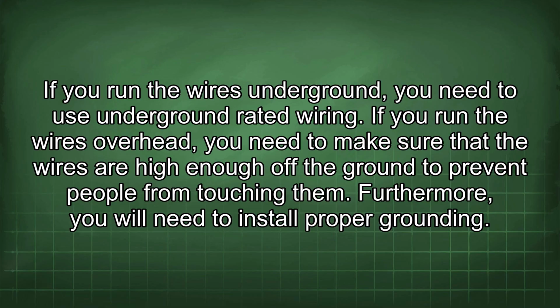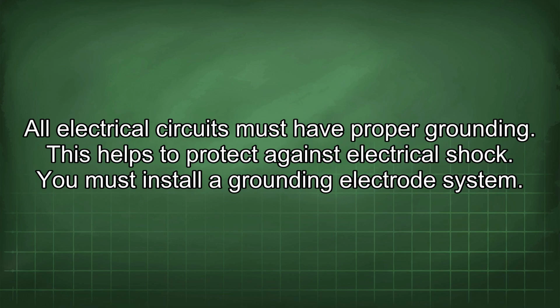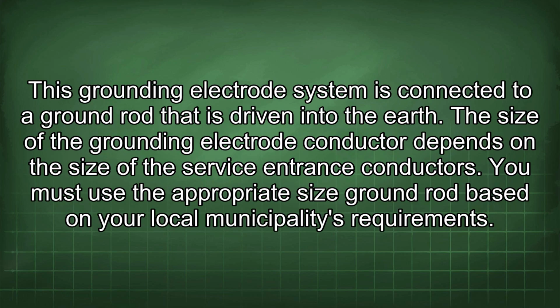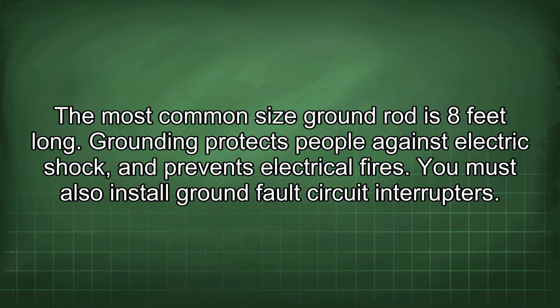Furthermore, you will need to install proper grounding. All electrical circuits must have proper grounding. This helps to protect against electrical shock. You must install a grounding electrode system. This grounding electrode system is connected to a ground rod that is driven into the earth. The size of the grounding electrode conductor depends on the size of the service entrance conductors. You must use the appropriate size ground rod based on your local municipality's requirements. The most common size ground rod is 8 feet long. Grounding protects people against electric shock and prevents electrical fires.